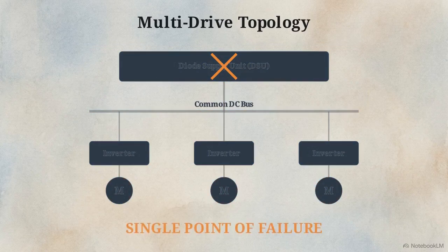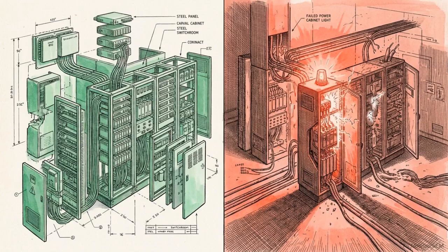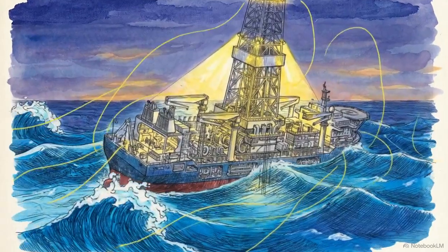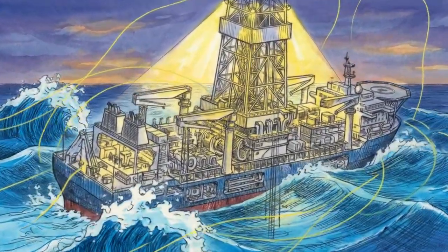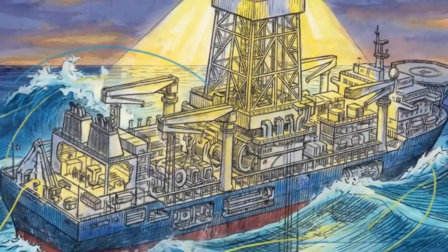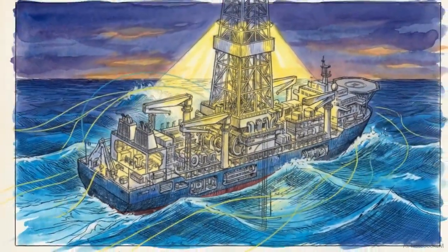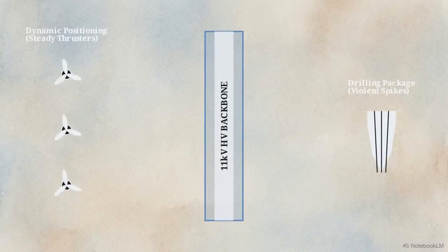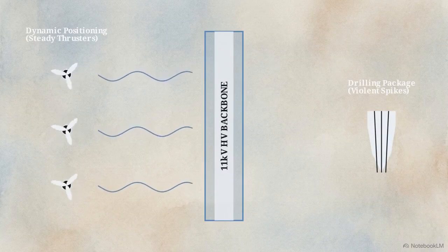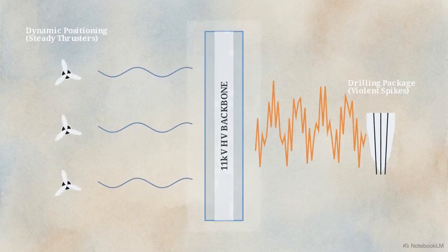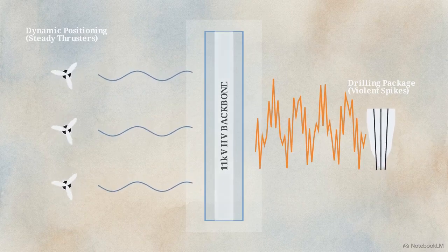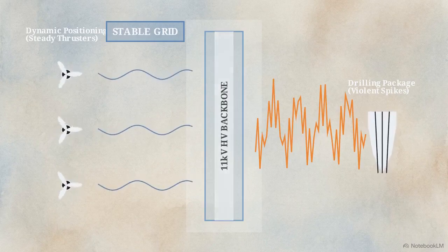But it introduces a vulnerability. A fault in the main rectifier will disable every motor on that bus. Architecting a rig is a balancing act between maximizing spatial efficiency and preventing single-point catastrophic failures. These topological decisions scale up to flagship projects, such as ultra-deep-water drillships requiring 90 megawatts of total installed power. An 11 kilovolt high-voltage backbone must orchestrate dozens of separate VSDs, balancing steady thruster loads for dynamic positioning against the violent power spikes of the drilling package.